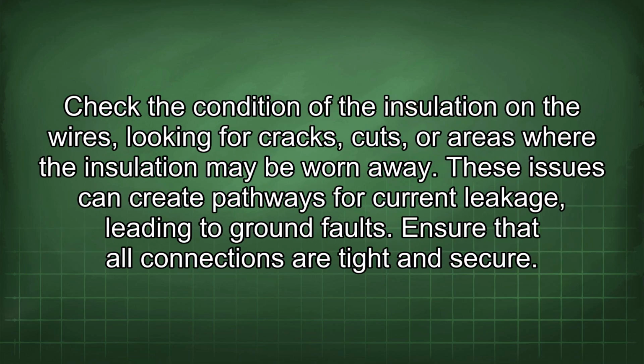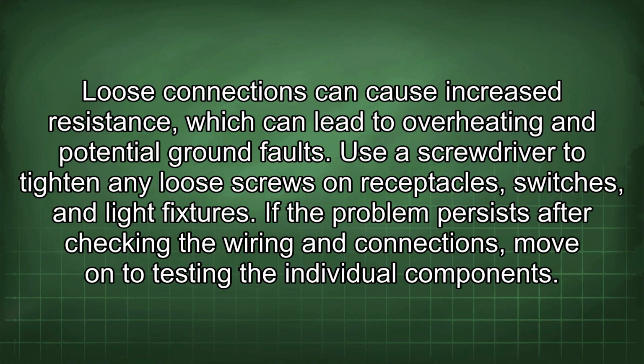Check the condition of the insulation and the wires, looking for cracks, cuts, or areas where the insulation may be worn away. These issues can create pathways for current leakage, leading to ground faults. Ensure that all connections are tight and secure. Loose connections can cause increased resistance, which can lead to overheating and potential ground faults. Use a screwdriver to tighten any loose screws on receptacles, switches, and light fixtures.